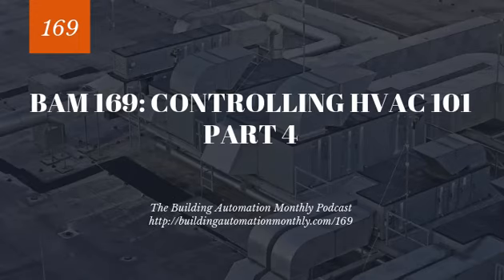Yes, that is more than 4 times the amount of energy to change state from 212 degree water to 212 degree steam. So that is why steam is used on large campuses, because you have 970 BTUs packed into that 1 pound of steam. So when you pressurize steam, you can see that you've got a lot of energy within that steam. Now, there are 2 types of steam, right? You've got dry steam, which contains the most latent heat for proper heat transfer, right?